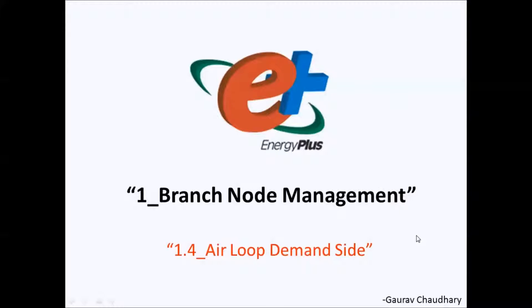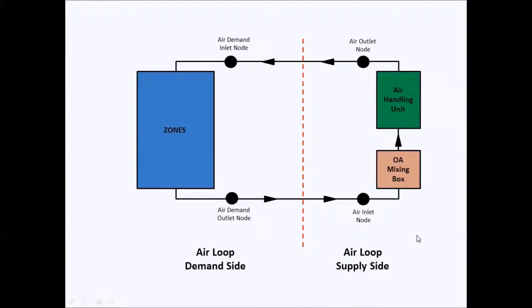We can distribute the air loop into two sides: demand side and supply side. The supply side would contain the AHU and an OA mixing box where outdoor air is mixed. The demand side would be the zones and the VAVs — this is where the air is actually required. For zone G and zone H we'll make two VAVs, and for the remaining zones we'll make one VAV each.